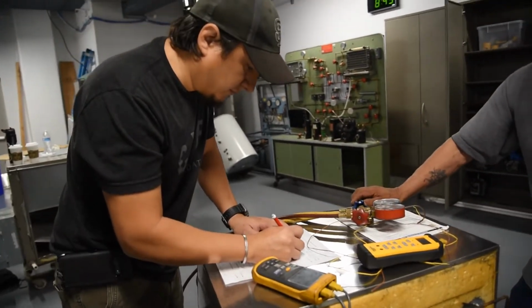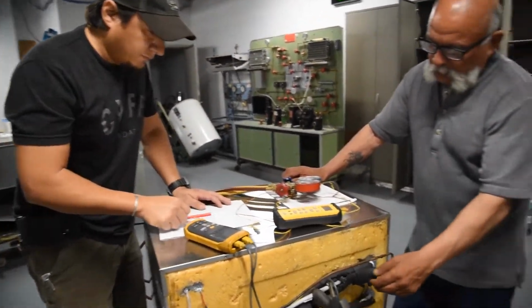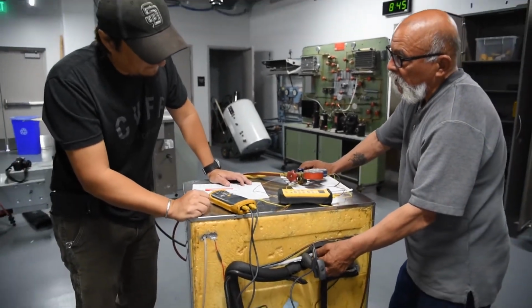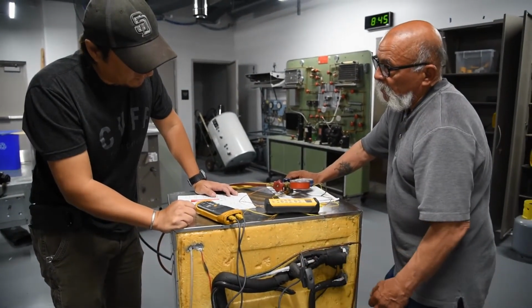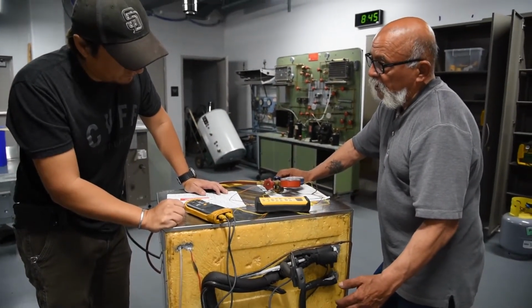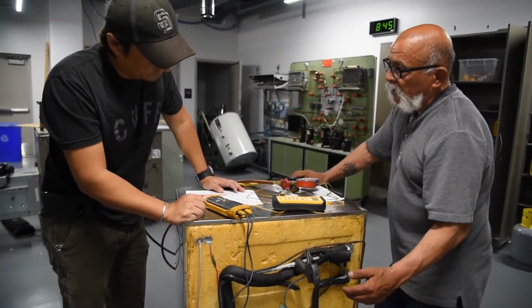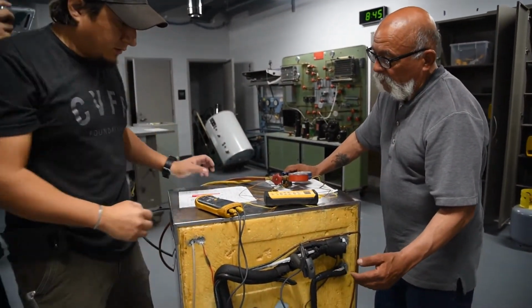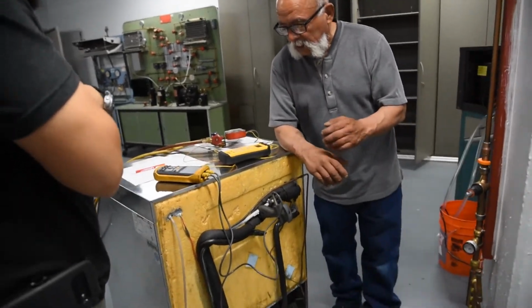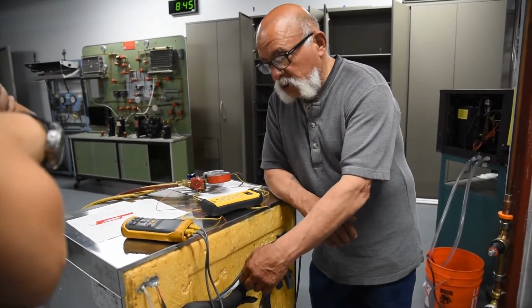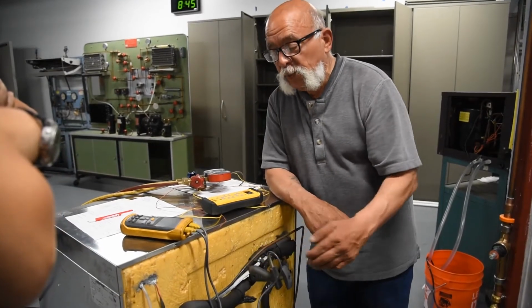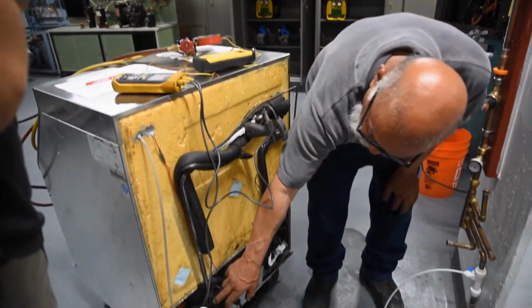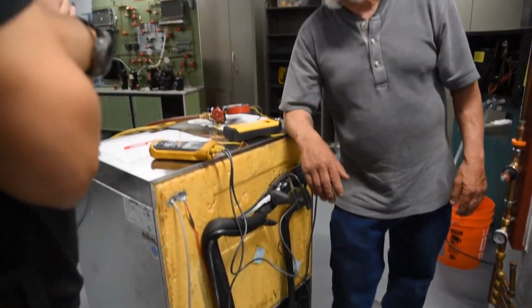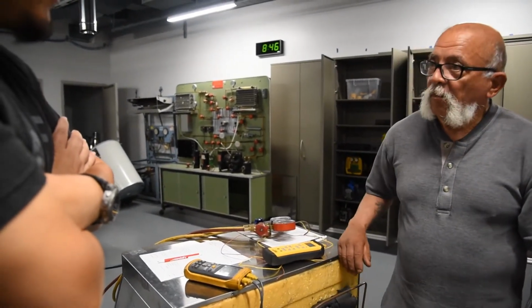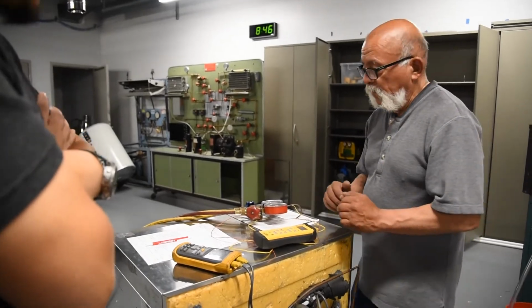Okay, 5.5 superheat. What is that telling us about liquid coming out of the evaporator? The lower the superheat, the more liquid has potential for coming out of the evaporator. Okay. But we don't need to be concerned about the superheat coming out of the evaporator getting to the compressor, because by the time it leaves the heat exchanger, the temperature is already back up. Oh, okay. So there's no risk of flooding the compressor because the heat exchanger is taking care of that. Yep. Interesting. It is.